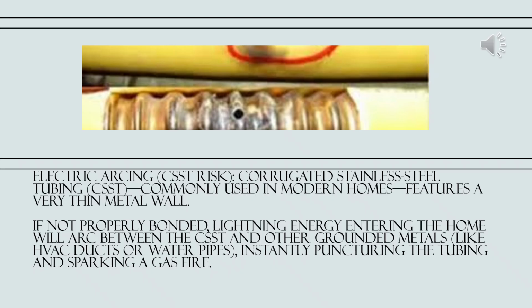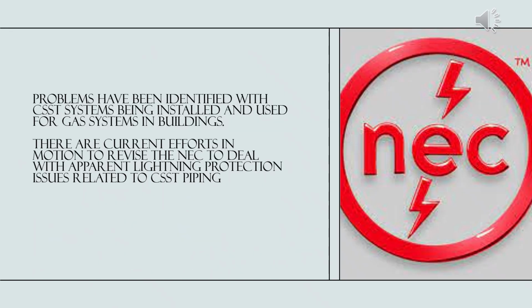This corrugated stainless steel tubing, commonly used in modern homes, features a very thin metal wall. If not properly bonded, the lightning energy entering the home will arc between the CSST and other grounded metals like HVAC ducts or water pipes, and it can cause a puncture, which of course then leads to gas getting out, and of course then leads to a house fire. There is history and lots of problems that have been identified with the CSST systems being installed and used for gas piping systems in buildings. Currently, there are efforts underway to deal with this in its different aspects.